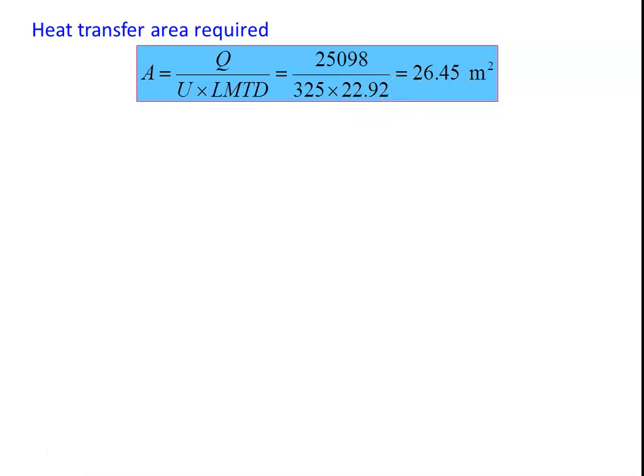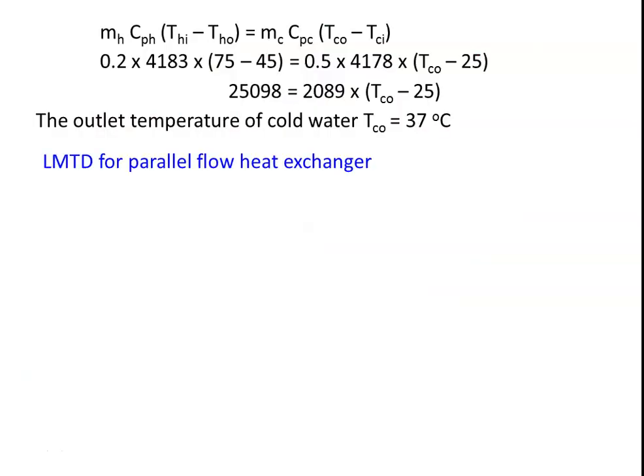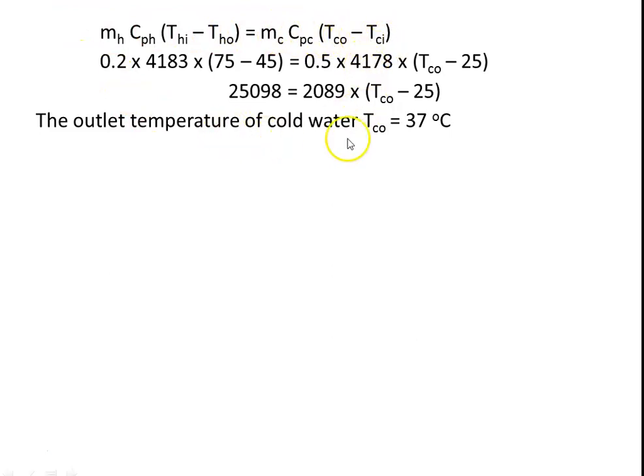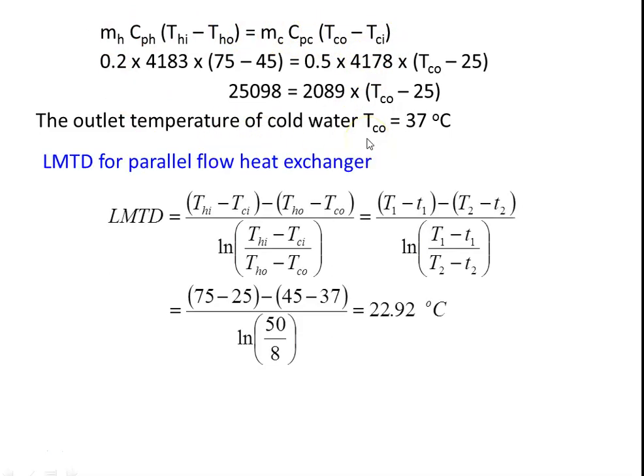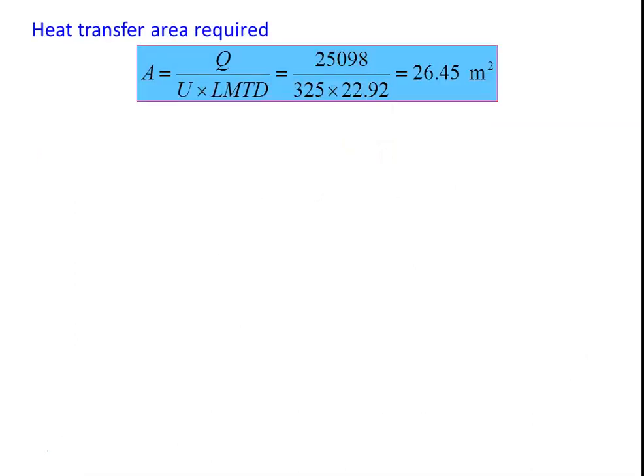So that is what you have to calculate — the area of the heat exchanger. The procedure is: use the heat balance to find outlet temperature, calculate the LMTD, calculate U, then substitute into A = Q/(U × LMTD) to find the area required for heat transfer.